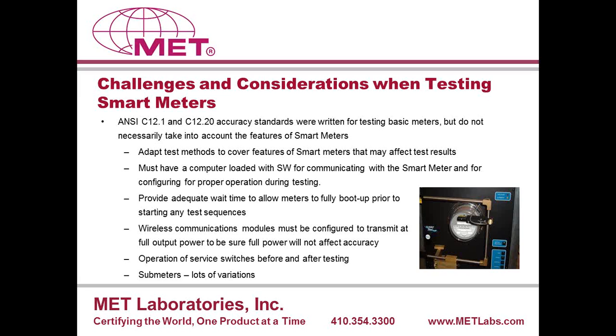Service switches, we need to make sure that they operate during certain points of the testing. We would request that support equipment be sent along with the meters as necessary so that we are properly operating the features of the meter during testing, before, after, during, depending on the test. But the point is that we are operating the meters, for example, the service switches, communicating either locally with a computer loaded with software or the website, what have you, so that we're looking at registers not just at the meter, but also remotely. It's a case-by-case situation, depending on what the product actually is. But these are some of the considerations that we've got to get into when we start up a test program. And all this is looked at, of course, when the request for quotation initially comes in.